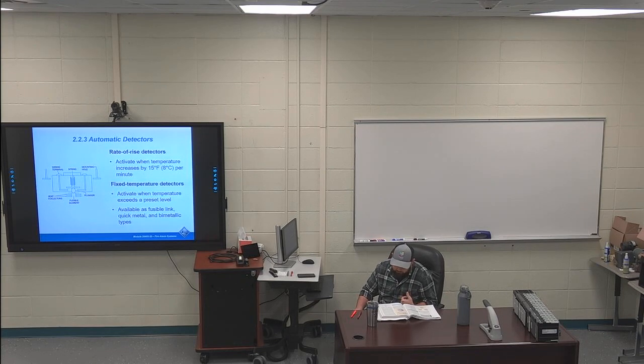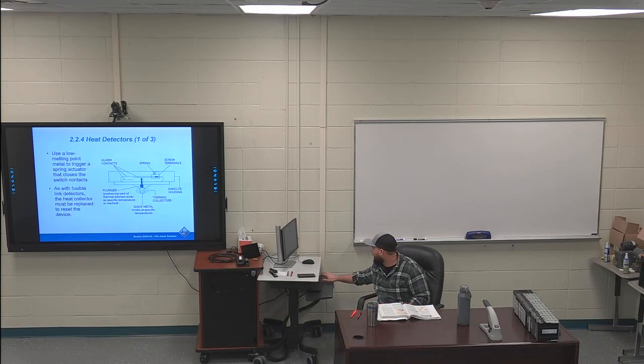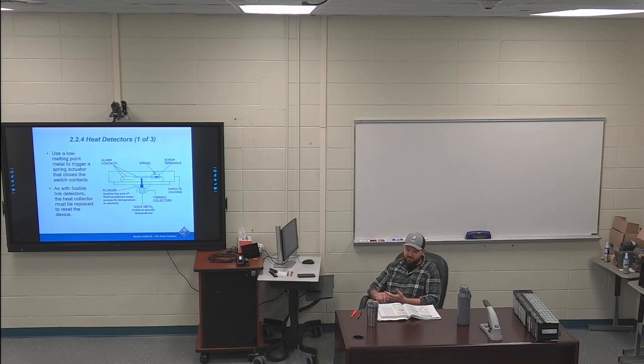Page 11, 224, heat detectors. First 3 sentences in heat detectors of 224 are highlighted. 2 major types of heat detectors are in general use. One is the rate of rise detector that senses a 15 degree per minute increase in a room or area temperature. The other is one of several versions of a fixed temperature detector that activate if the room exceeds a rating of the sensor.